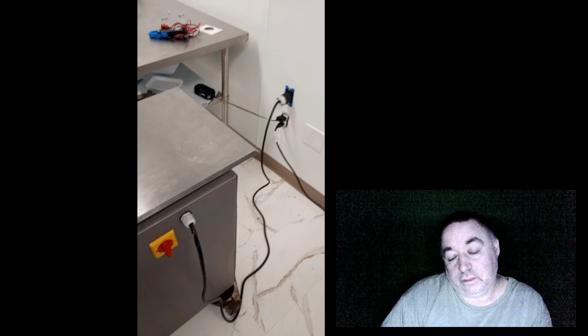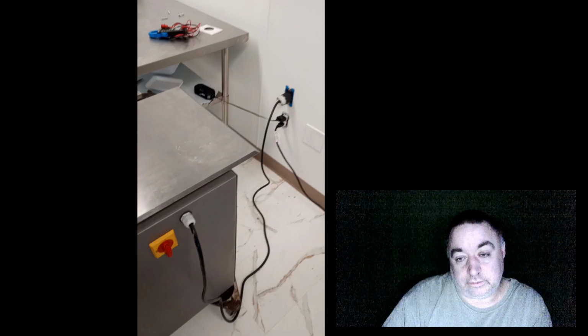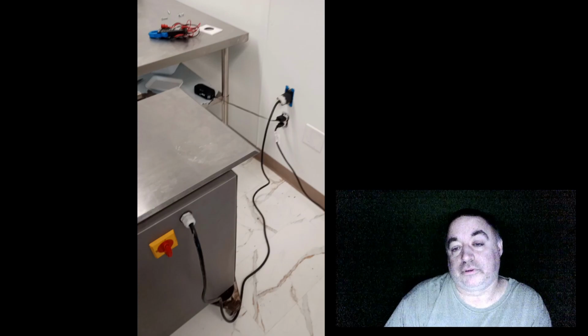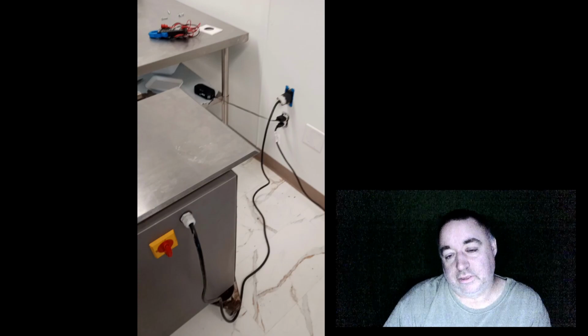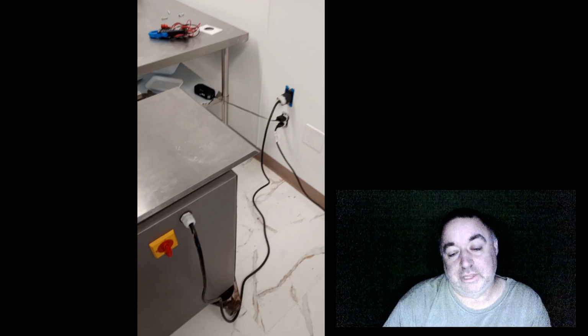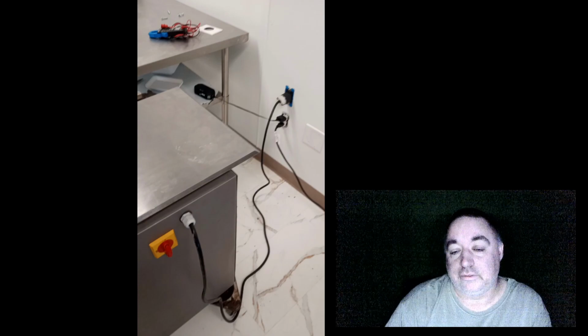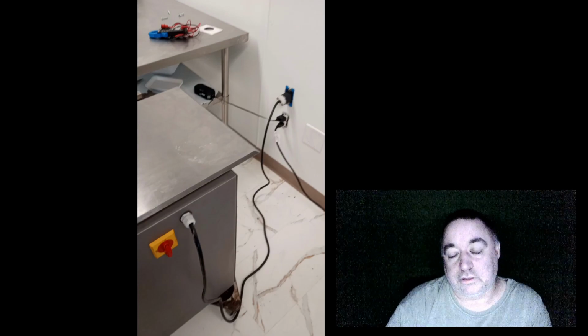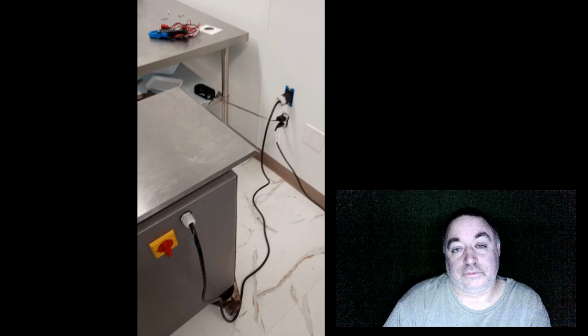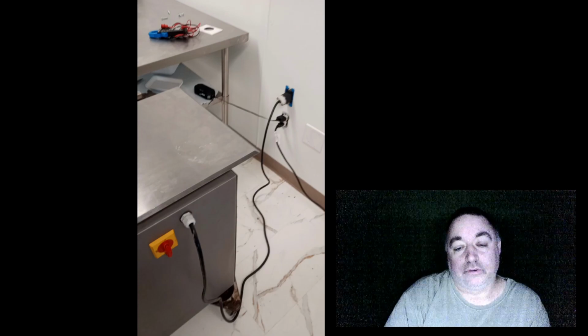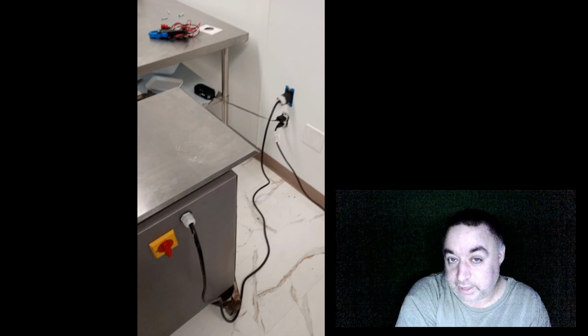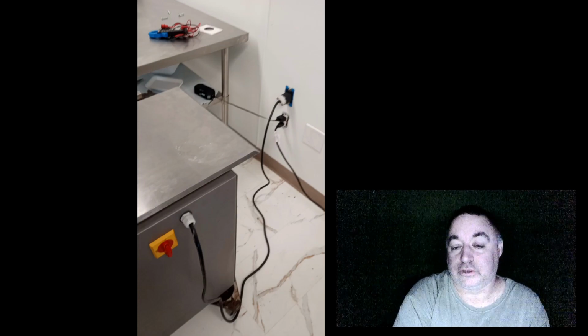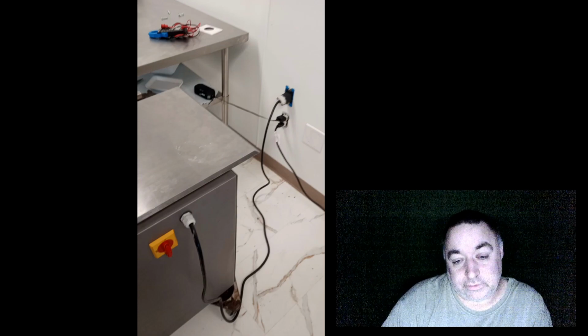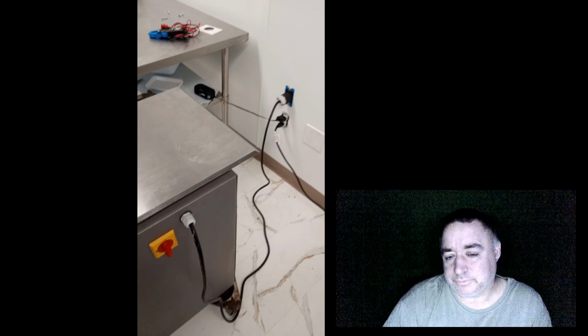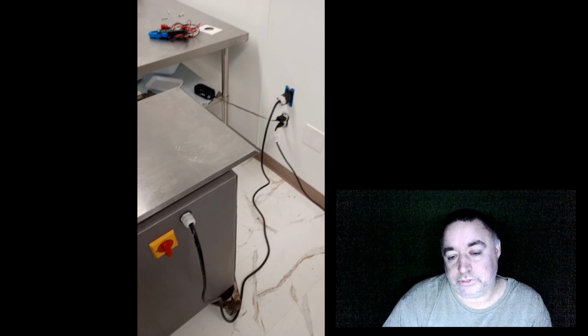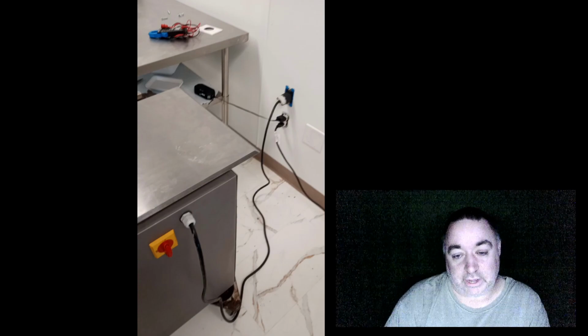Bad control board. So, in your opinion, do you think it's a fault? First of all, if that ground was pulling that kind of power, I didn't get into that with them, because that's their machine, has the wiring that the specs call for, that's all I'm concerned with. But I don't know, the loose circuit breaker, that had to be it, because he said it was working for a week like that, which I find hard to believe, as loose as those were, because that's how I found it. So there could have been some arcing going on that whole time, that ultimately the board just got upset with seeing this voltage coming and going and decided to crap out.